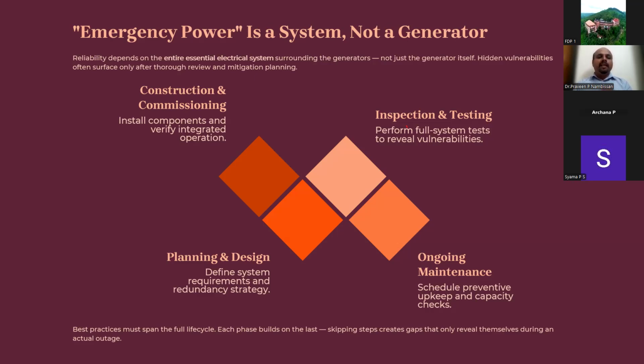Then planning and design - define system requirements and redundancy strategy. We have to have a backup for the particular system, especially in the operation theaters. If one light fails, the other light has to do the same. The grid has to give a constant, reliable power source.